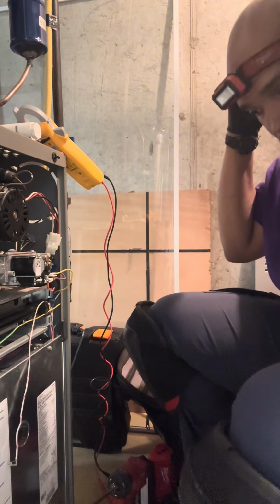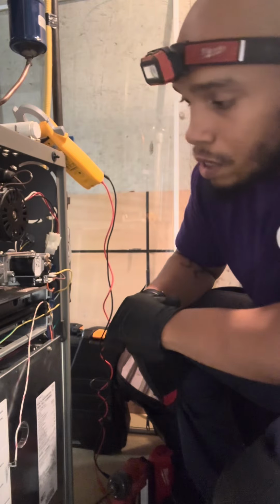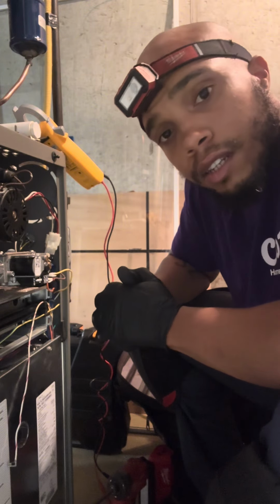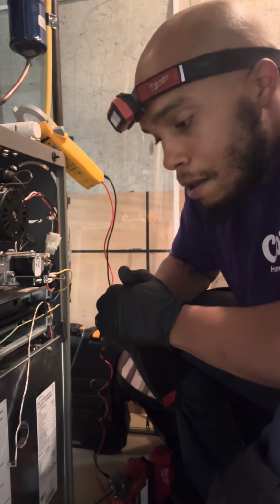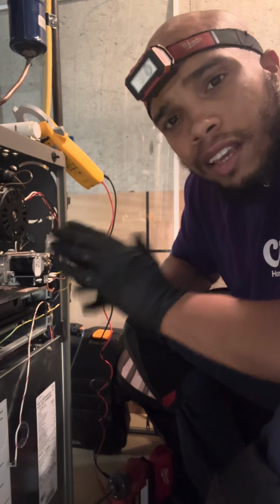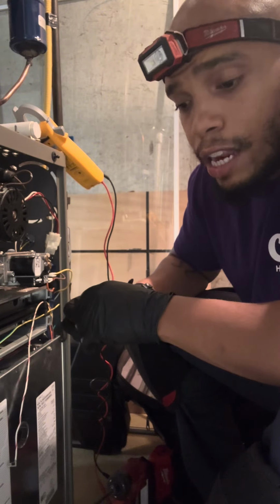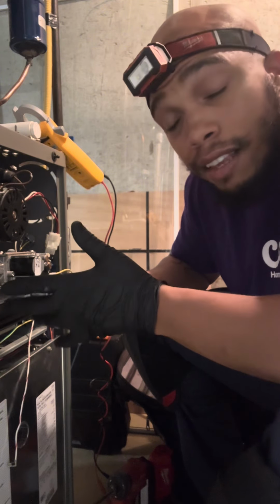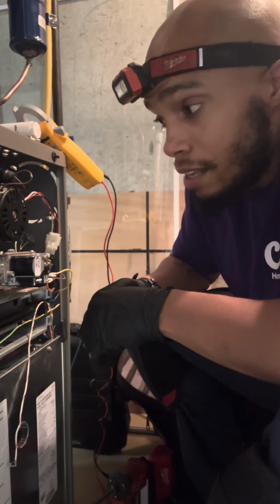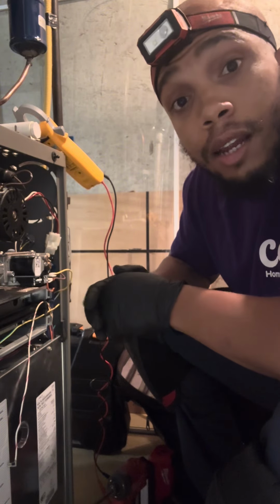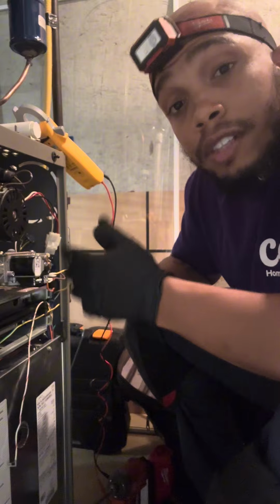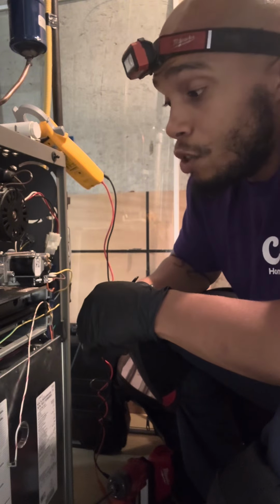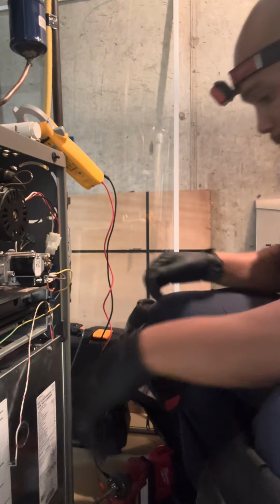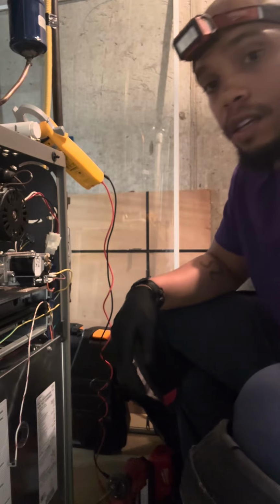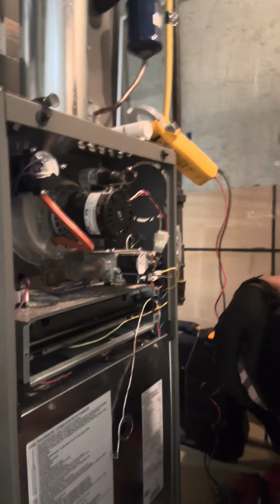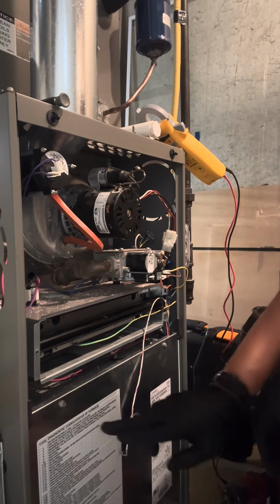So far on this model, the heat exchanger does have a few concerning spots. When I look inside there, I don't want to see any deep rust or any cracks. Anything like that is always a bad sign, because like I said, that metal comes nice and shiny out of the box, and over the years, as that metal wears away, you will be exposed to cracks. All right. With that being said, I'm now going to check the blower compartment.